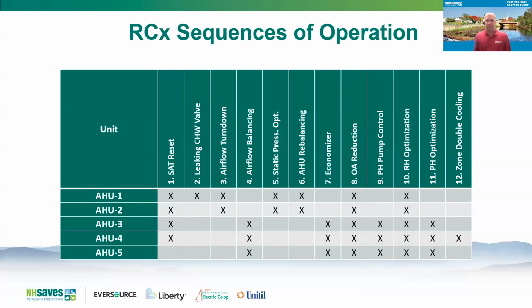Outside air reduction, this is another big one where oftentimes air handlers bring in too much outside air. And balancing the outside air to what the space actually needs and further implementing demand control ventilation can be a great opportunity. Demand control ventilation wasn't a sequence here because of the lab nature of the space, but in many spaces it can be great. And then there's a few other sequences here for these 5 air handlers.